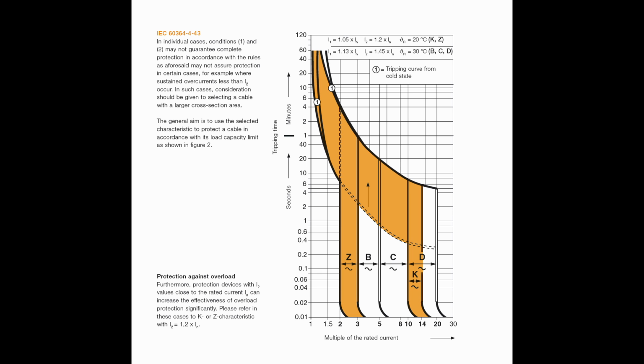And that little piece at the bottom where the line sort of starts to curve away in the other direction, that's actually where the mechanical parts of the circuit breaker come into operation, because no matter how much current you're going to apply, there's always going to be a certain amount of time for the mechanical contacts to open, hence it starts to curve away in the other direction as you get right down to the tiny times at the bottom. But suffice to say, they're all going to trip in that sort of range in the middle. It just depends on what the actual type is as to where the current required is.